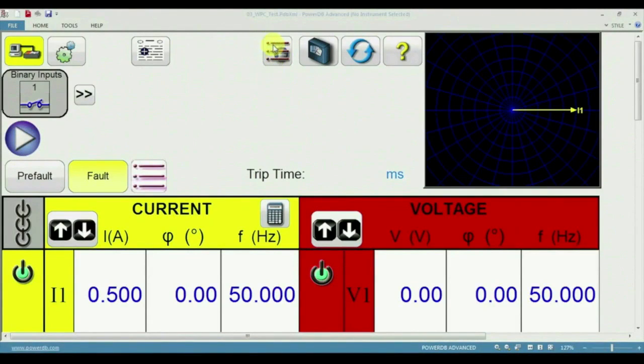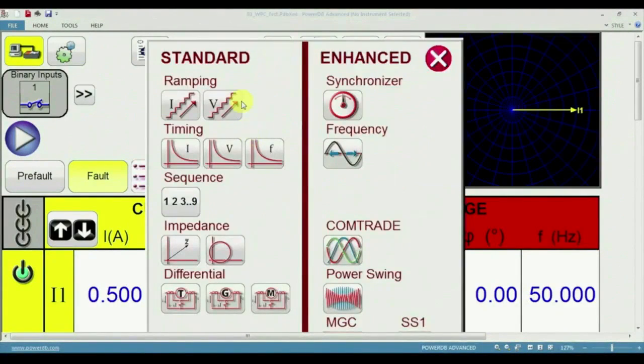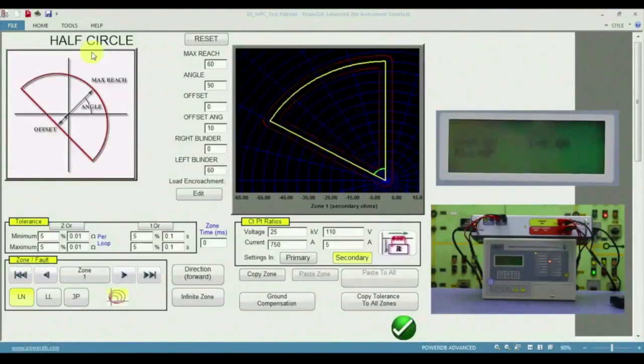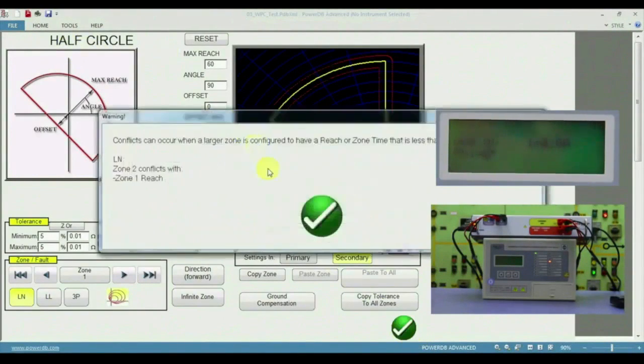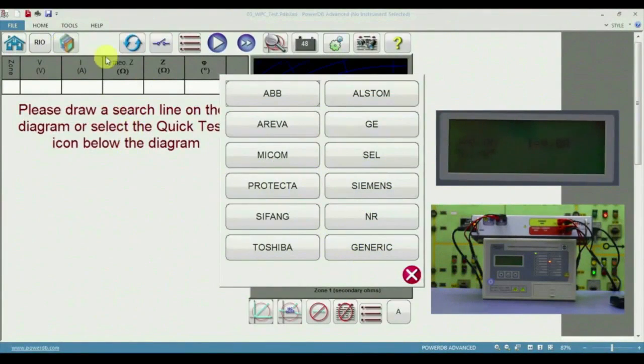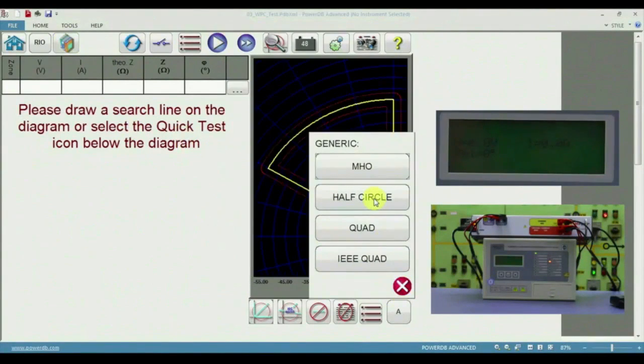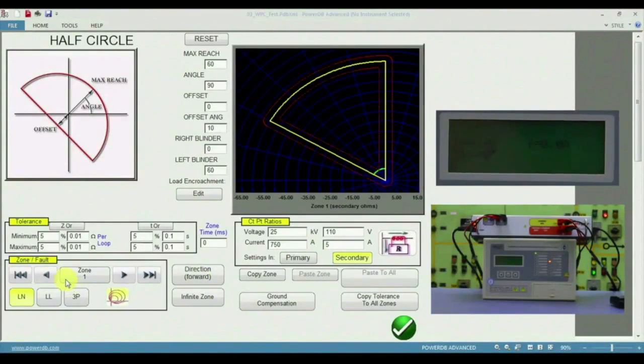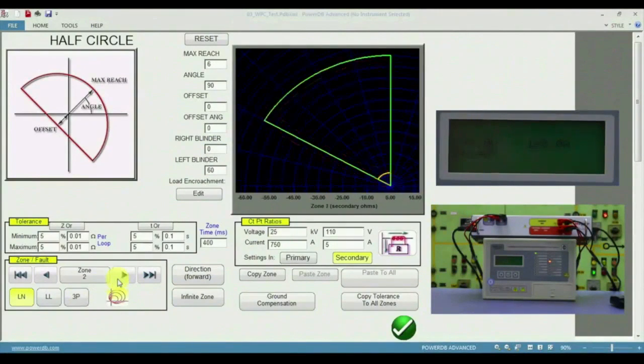So in RTMS software, let's use the standard distance protection module. So click here in the advanced menu. Click on the impedance option. So in the library, you can click on half circle. Here, click on this library, click on generic and click on this half circle option. In half circle option, you can select zone 1 on phase to ground and you can enter the maximum reach as 60. This is in line with the relay settings. The angle, offset, all these are configured to ensure that the region lies in the second quadrant. Zone 2 is configured as 2 ohms. This is to ensure that you show the reach area between 2 ohms and 60 ohms.